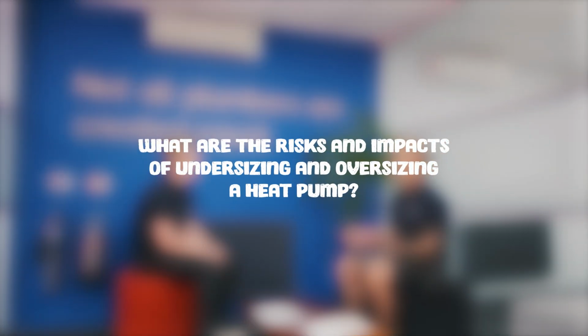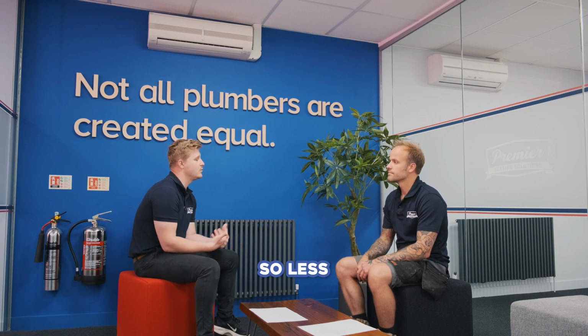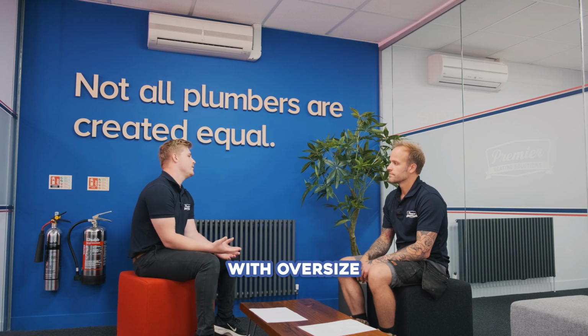So what are the risks and impacts of both undersizing a heat pump and oversizing a heat pump? With undersizing a heat pump, you run the potential of the heat pump not actually being able to heat your property. And also, if it can heat the property, it will be at a high temperature, so less efficient. Now, the risk with oversizing a heat pump is high cycling, which again can lead to inefficient operation.